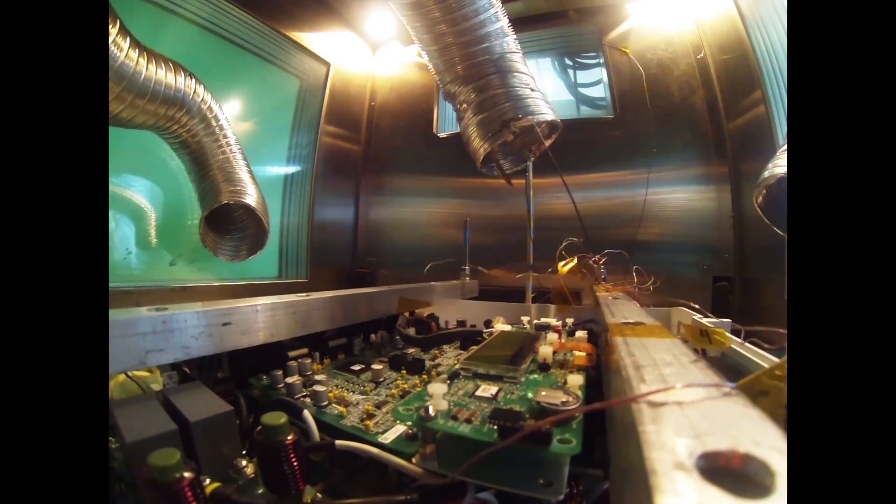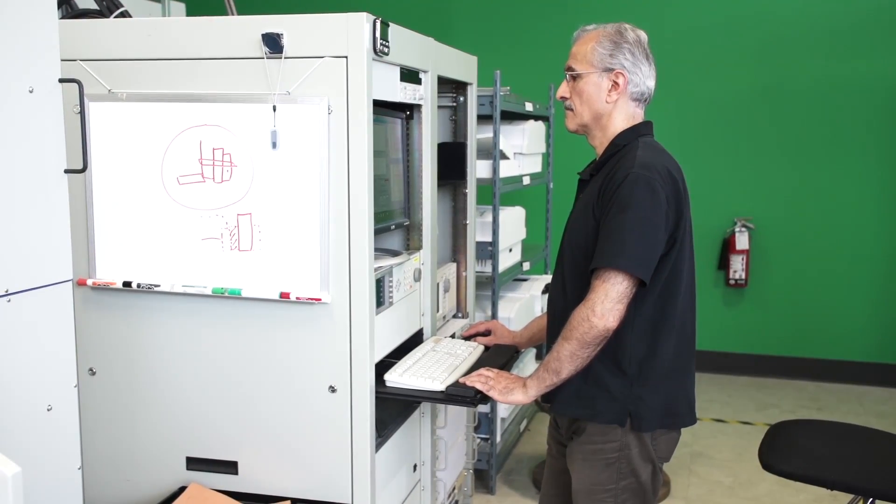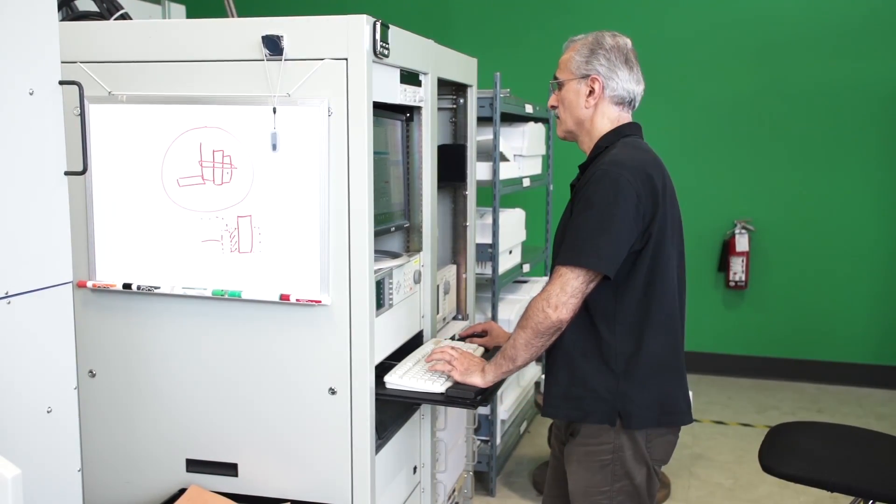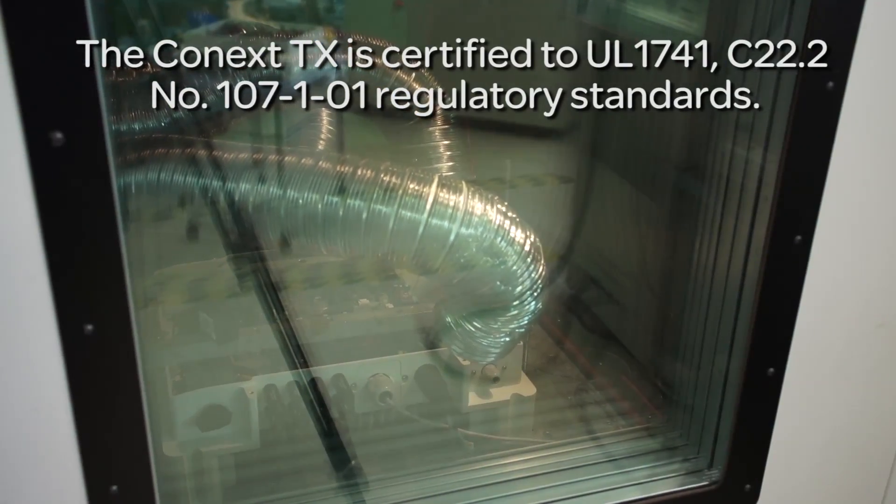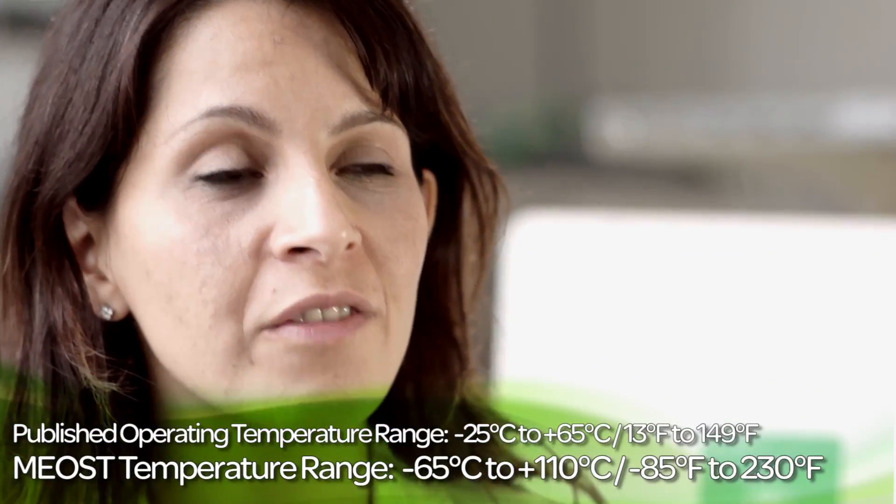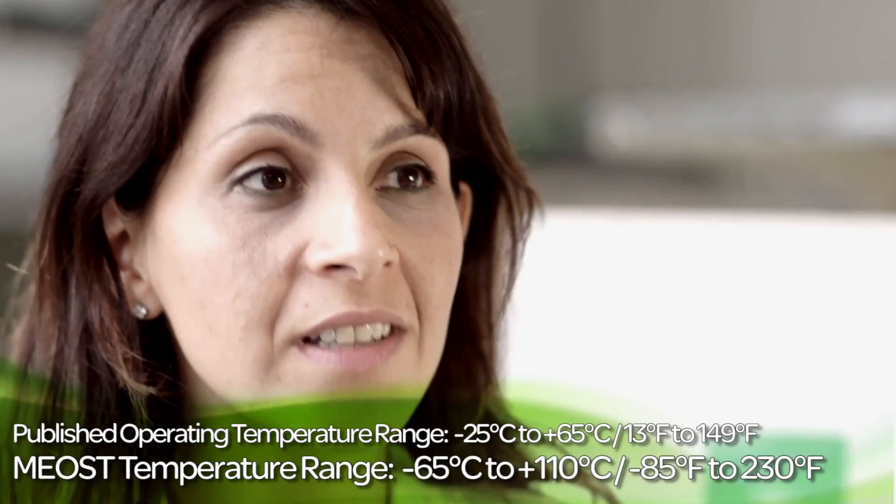Let's consider the case of our Conext TX grid-tie solar inverter. The unit that is being tested here is a 5 kilowatt inverter suitable for outdoor use. We specified that the product can be operated from minus 25 to plus 65 degrees Celsius, but in MEOST, we tested the product from minus 65 to plus 110 degrees Celsius, in combination with other stressors such as vibration, power, and frequency cycling, to uncover potential weaknesses which may occur over time in the real application.